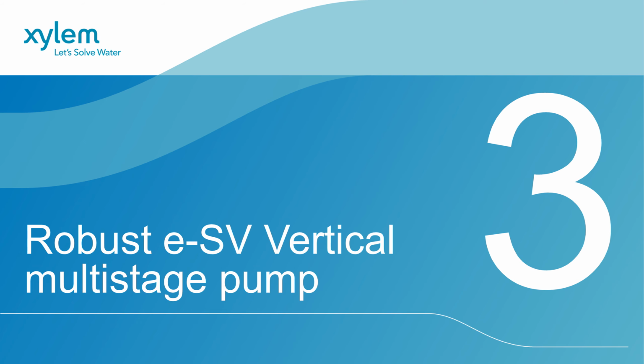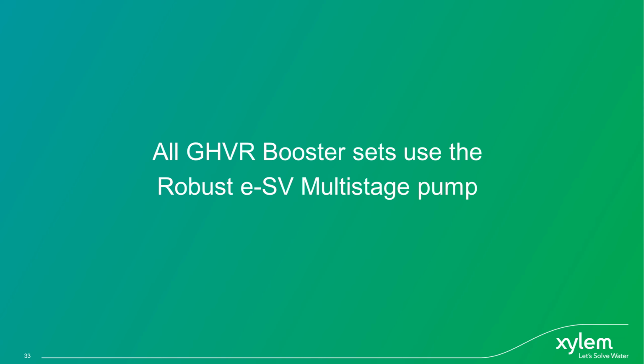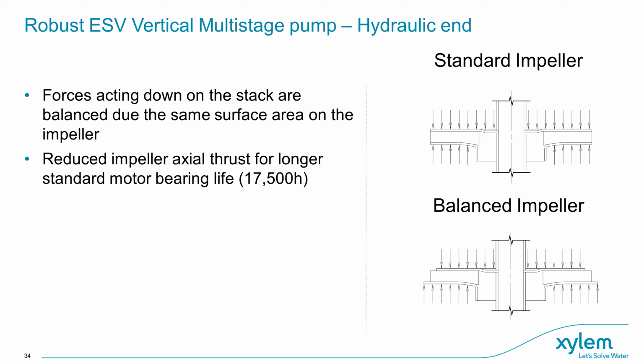We can now talk about the robust ESV Vertical Multistage Pump. And as the slide says, all GHVR booster sets use the ESV multistage. In terms of the hydraulics of the pump, to ensure the longevity of the unit, we use specially designed impellers to ensure that the axial force acting on the top and bottom sides of the impeller is balanced. This reduces strain on the hydraulic end and improves the lifespan of the motor bearings.